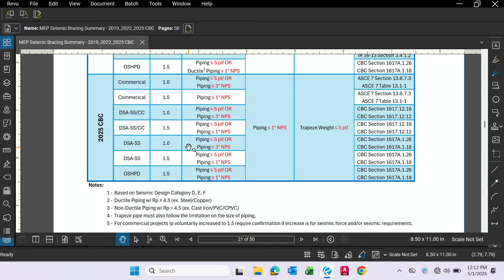I mentioned earlier that on some projects the design team or the owner can choose to override the code and increase the importance factor. If you run into those projects, make sure that you get confirmation from the team that they are aware that when they increase the importance factor, it will affect the bracing requirements. So you have to ask them, what do you want us to do? Do we just increase the force with an importance factor of 1.5, or do we need to follow the pipe bracing exemptions for the importance factor of 1.5? Okay. Any question before I move on? All right.